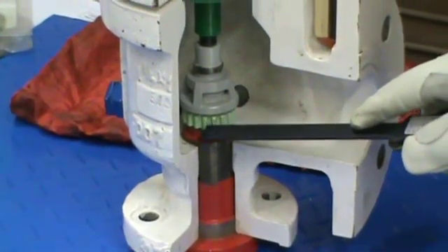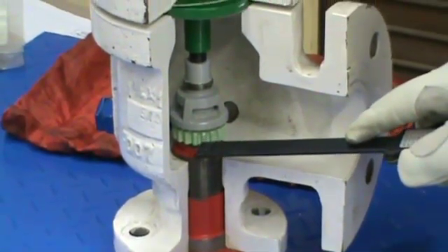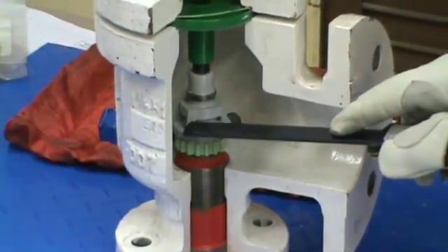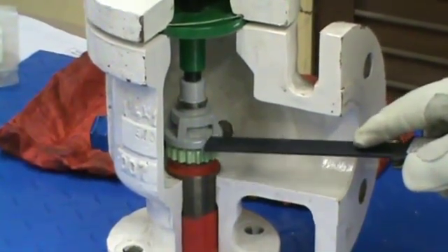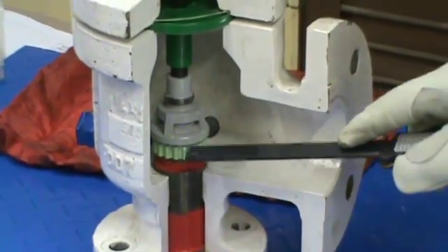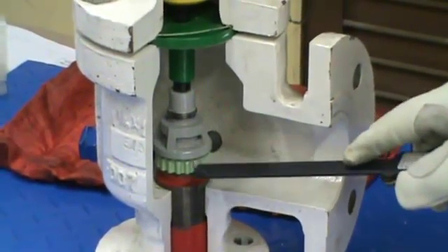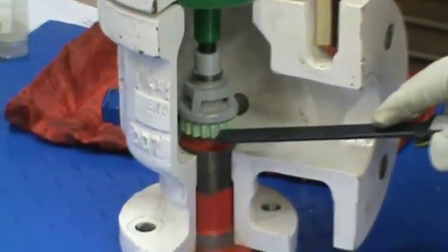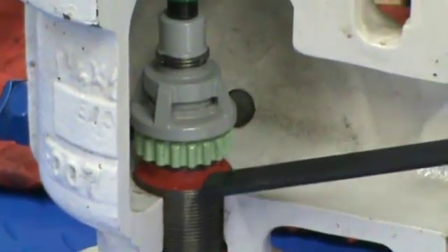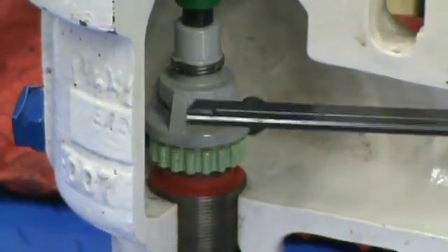Here is a ring which helps control your blowdown. This gray piece here is correctly called the disc holder. The disc which is inside of there is your second half of your seating surface. It makes contact with the top of the nozzle and that's what seals.